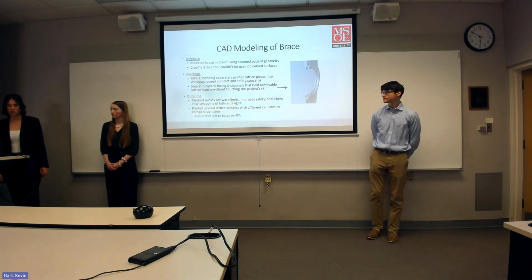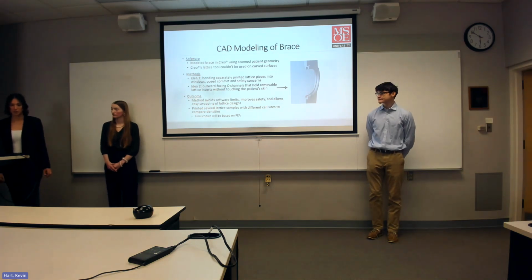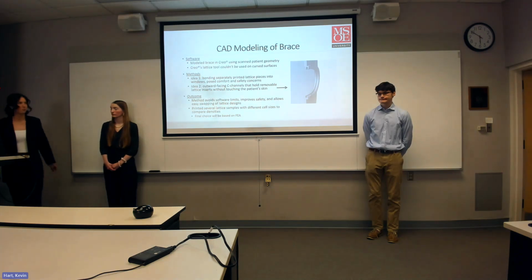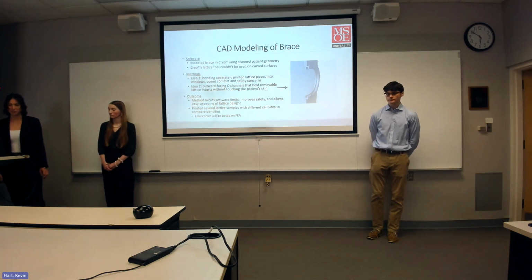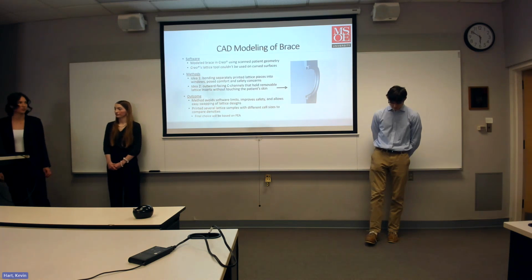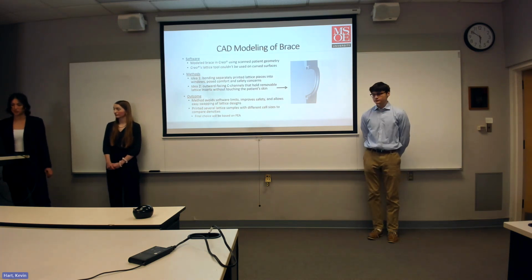Along with this, we printed several lattice samples with different cell sizes to compare the densities just by visually looking at them. But the final choice will be based on FEA results to maintain the structural integrity of the brace in the end.